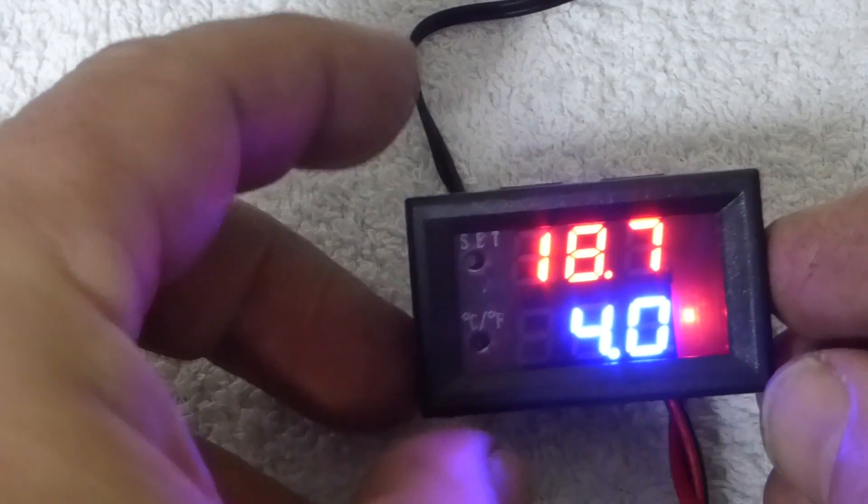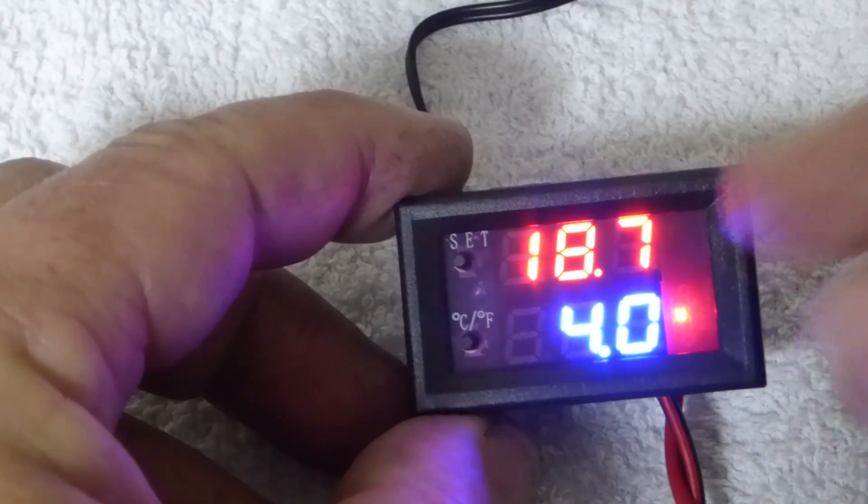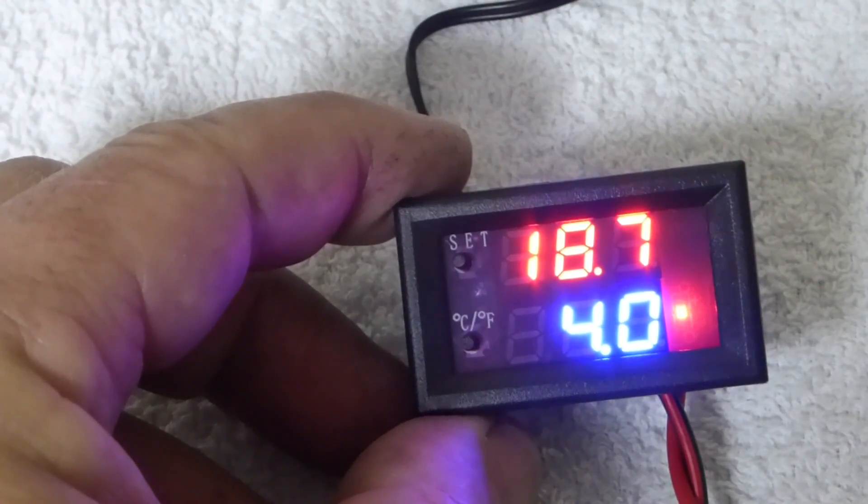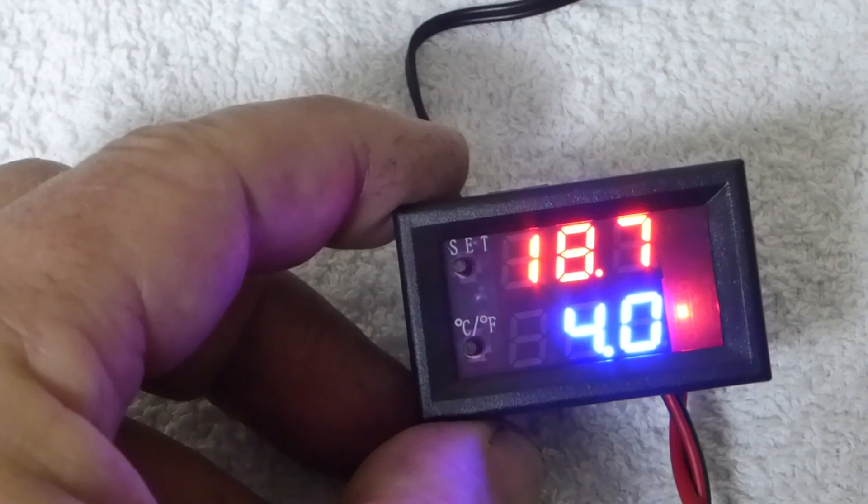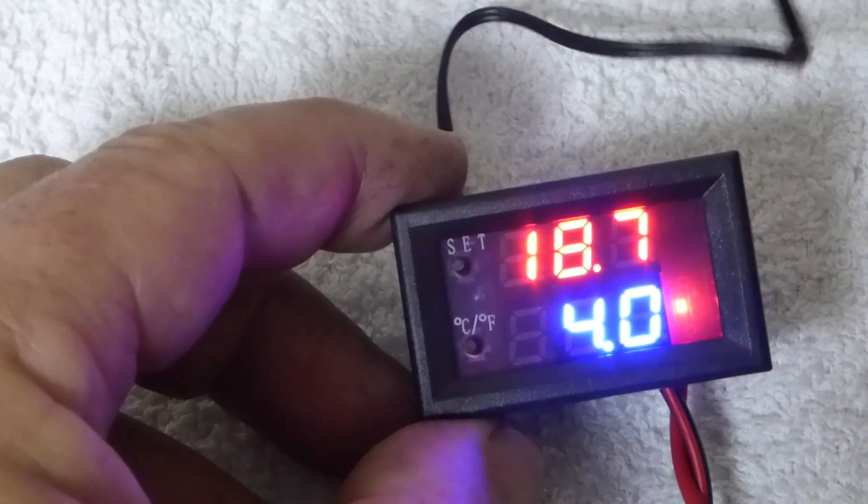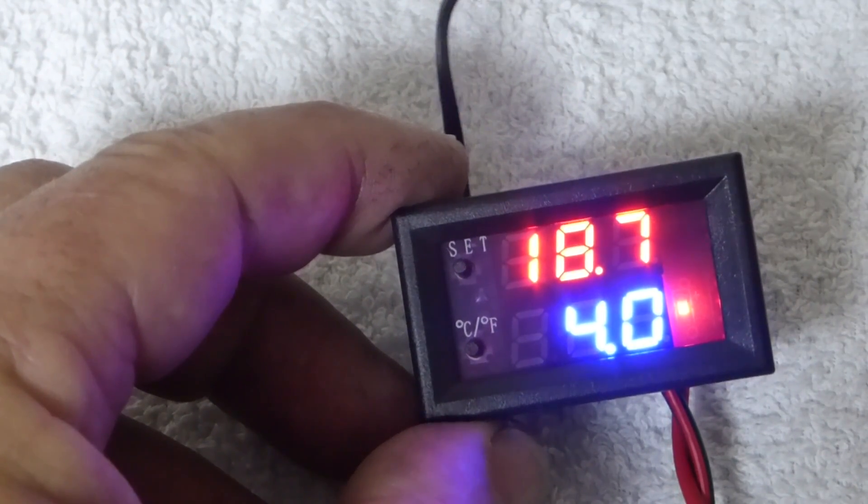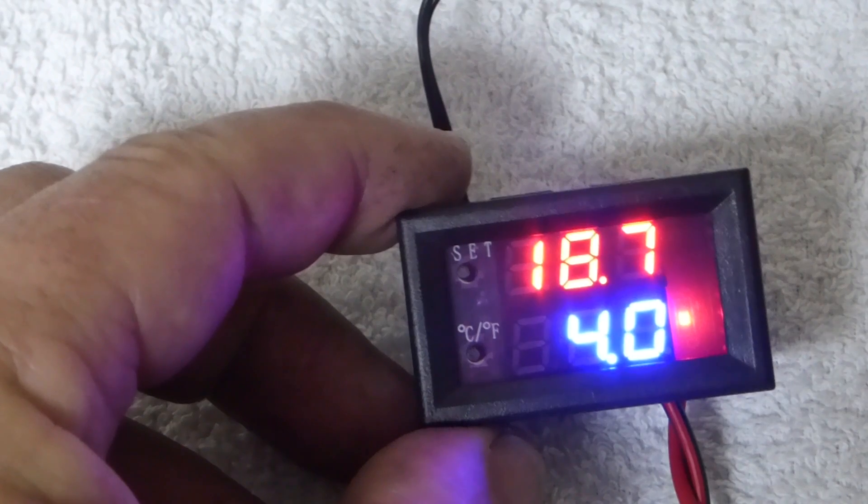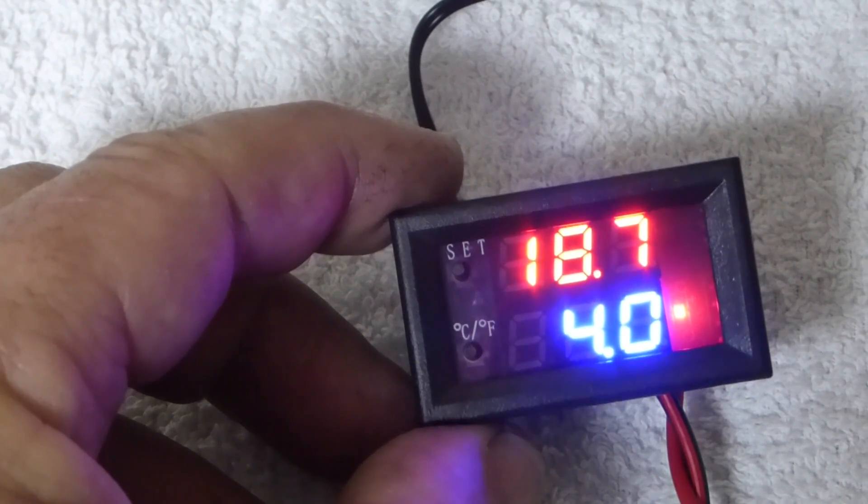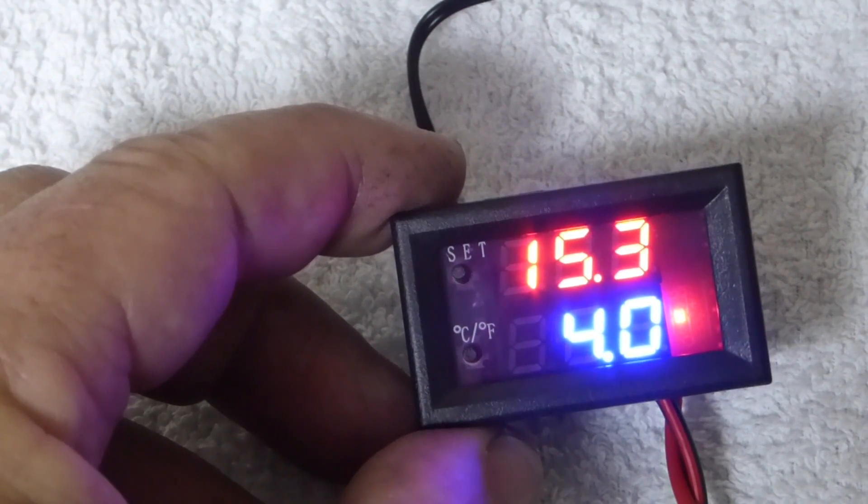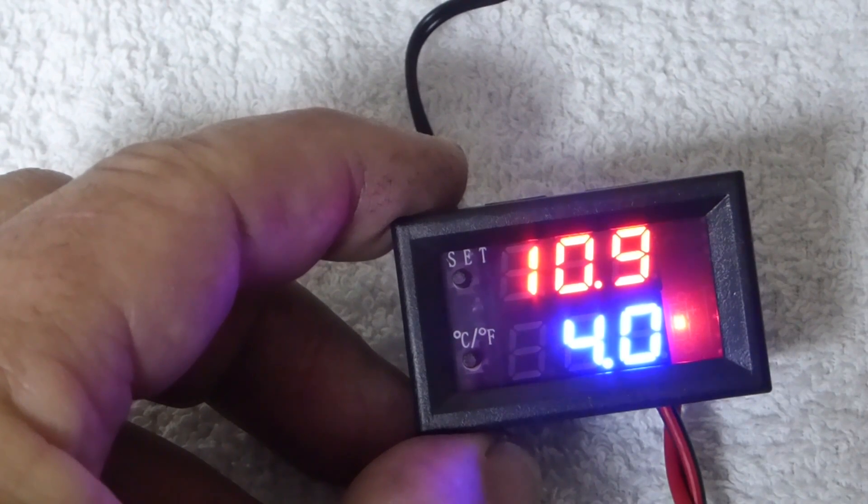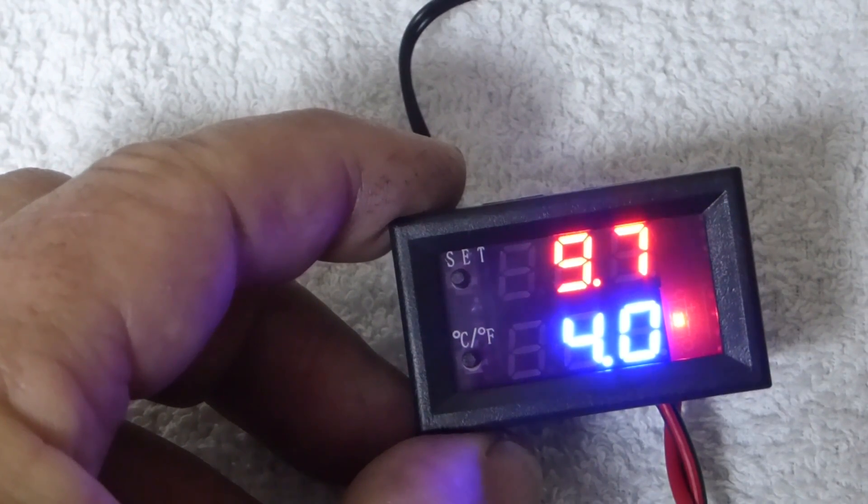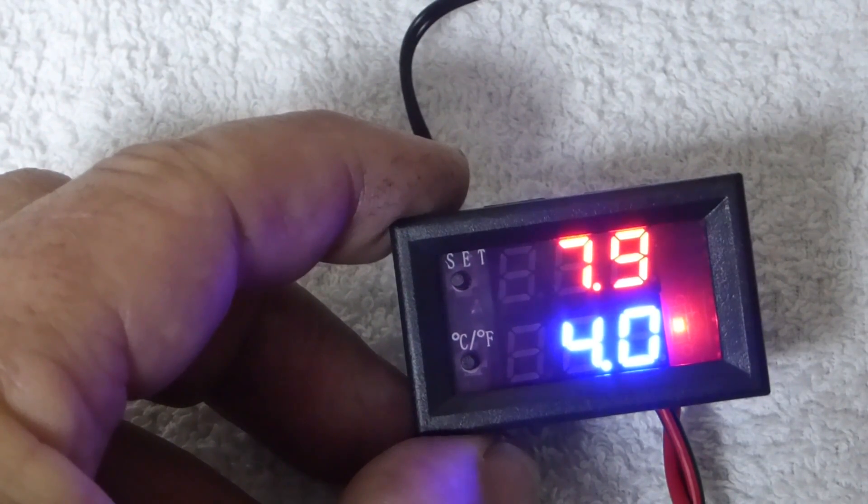Now technically the compressor is running because the room temperature is 18.7 degrees. Now I'm going to reduce that temperature by sticking the small probe into a glass of cold water and you'll see the temperature go down. And when it hits four degrees, technically the compressor will cut off.